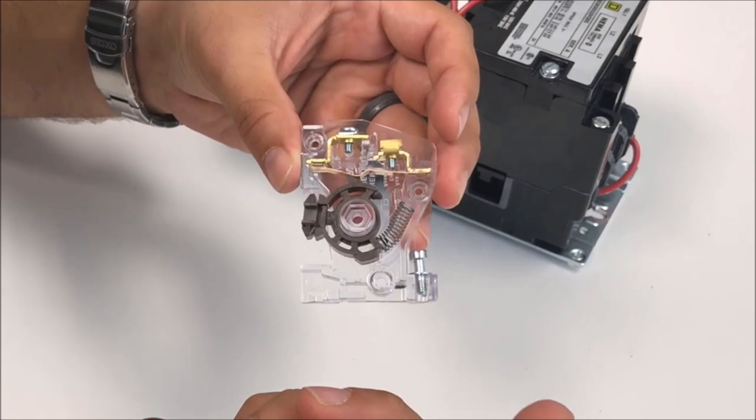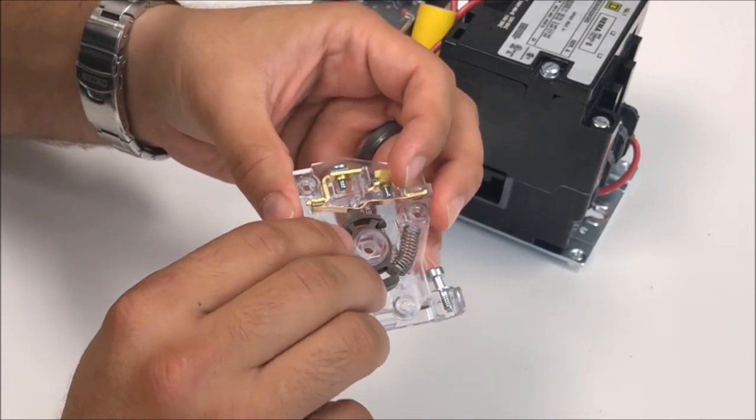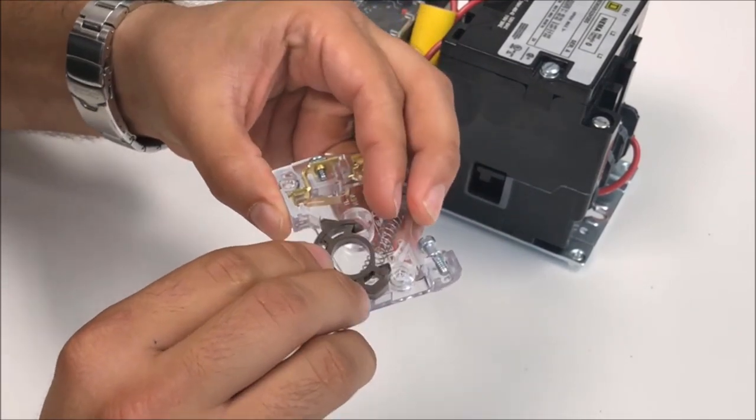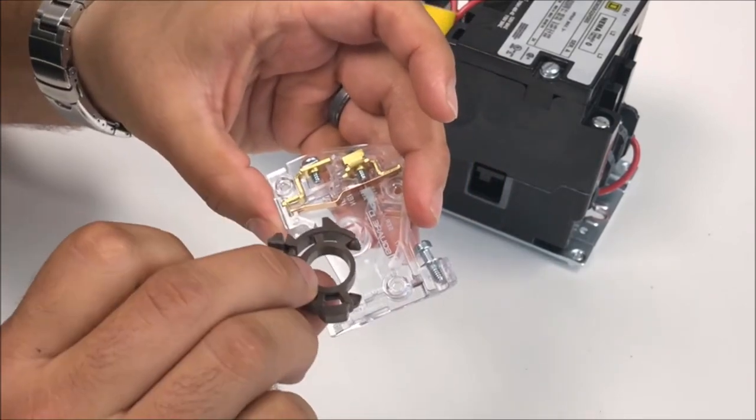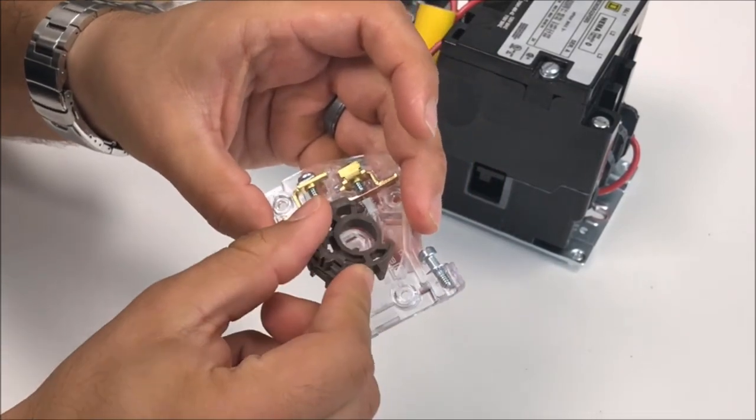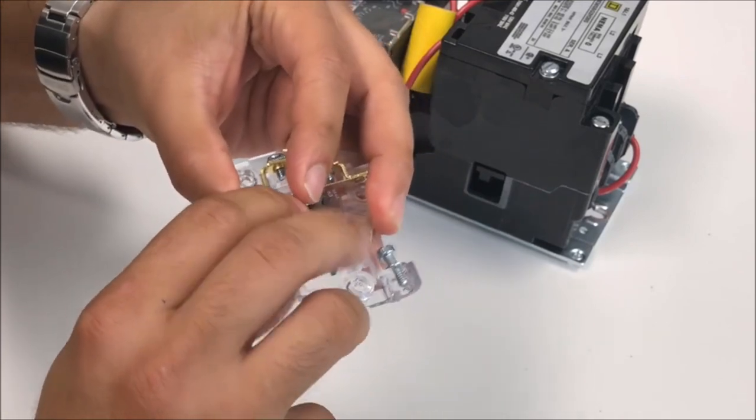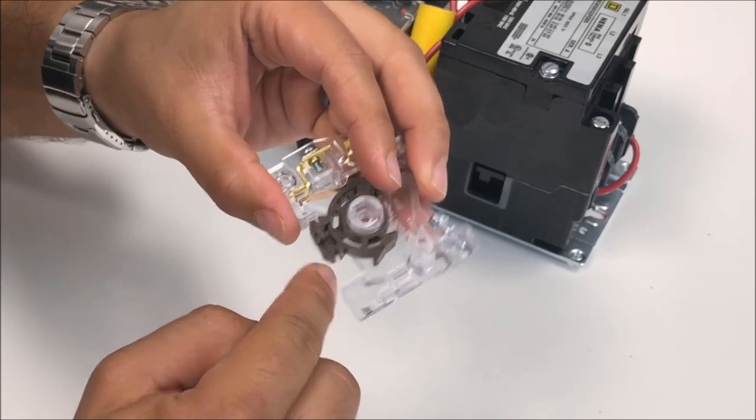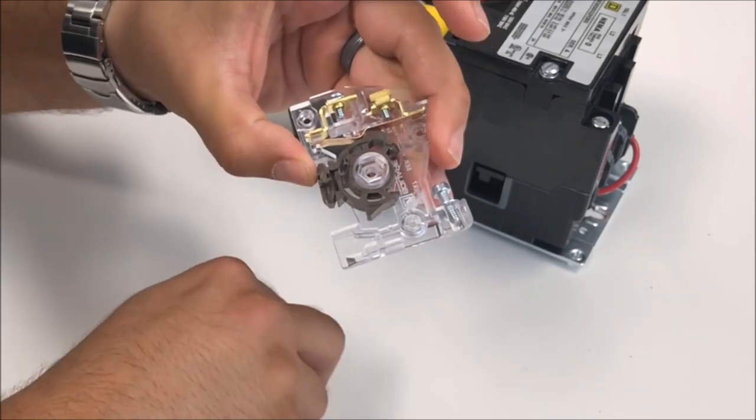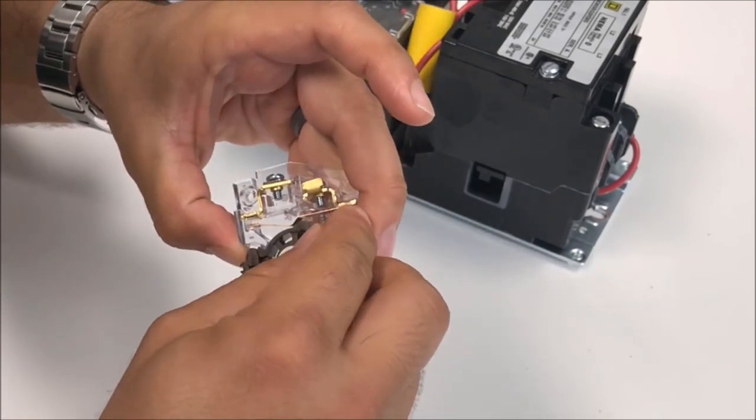In order to convert these, simple instructions are to remove the cam and the spring. You're going to take the cam, flip it over, put it right back here so the operating lever's on the outside of the device, and then reinsert your spring back into the same location.